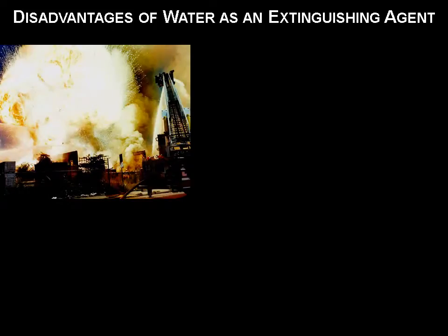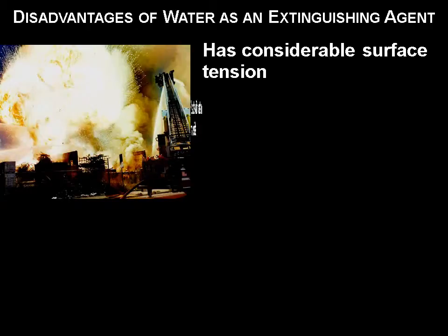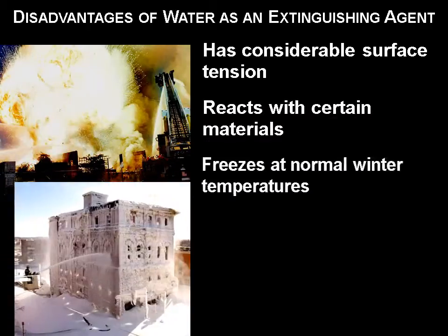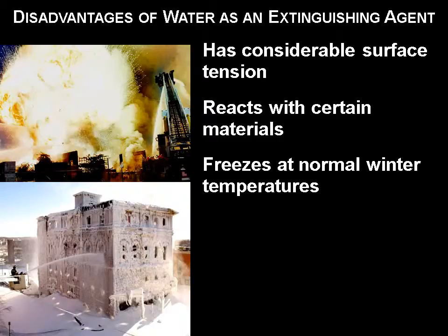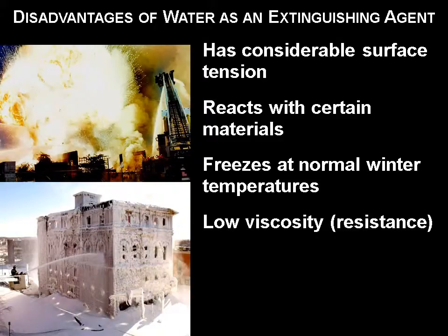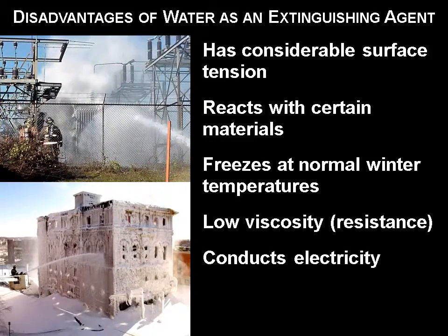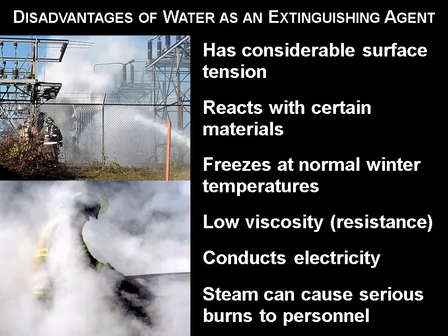The disadvantages of water as an extinguishing agent: has considerable surface tension, reacts with certain materials, freezes at normal winter temperatures, has a low viscosity or resistance, conducts electricity, and steam generated from the fire stream can cause serious burns to personnel.